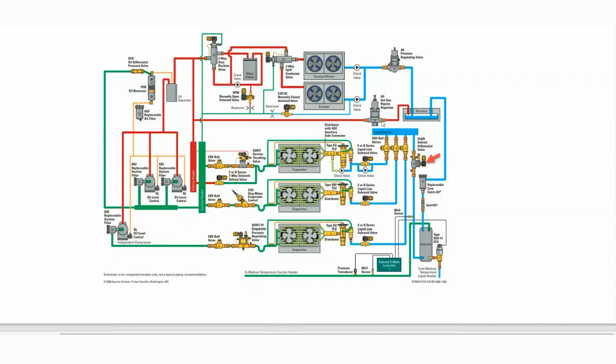Because when we're doing this, we're actually creating liquid. We're taking that hot gas, de-superheating it, making a latent heat exchange, which is really what's doing most of the defrosting, and then in turn going back up to the liquid header itself. Yeah, that evaporator is becoming a condenser, right? It's taking the ice that's on that evaporator coil and the lack of heat in that coil, and it's condensing that hot gas coming from the defrost header, and that's really what's doing the work.